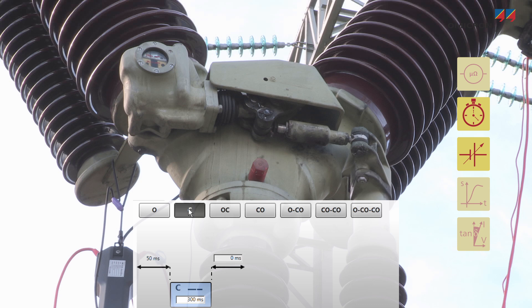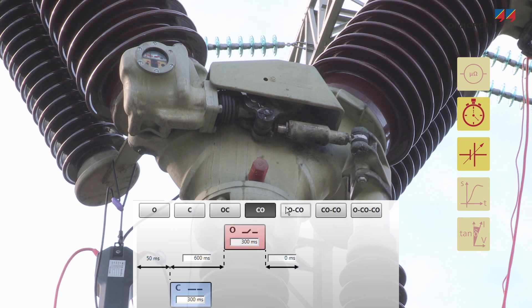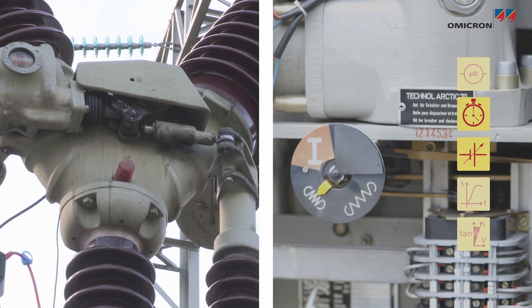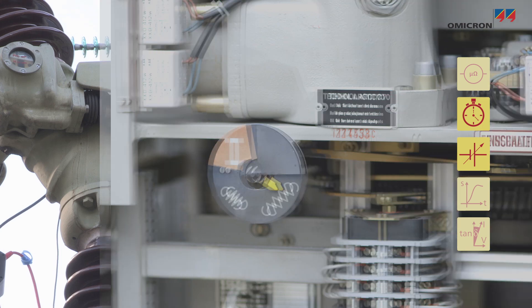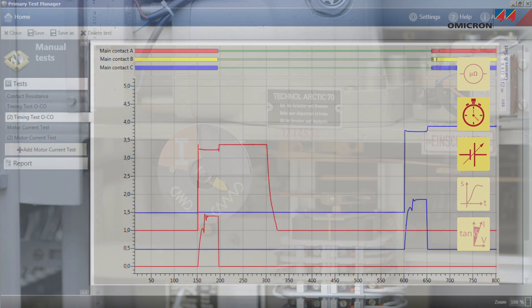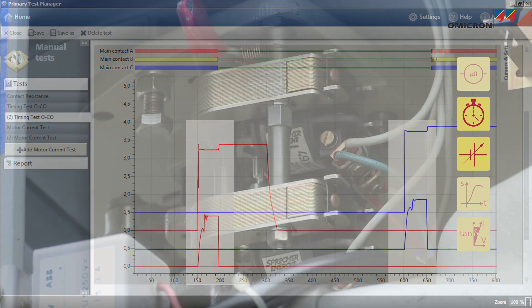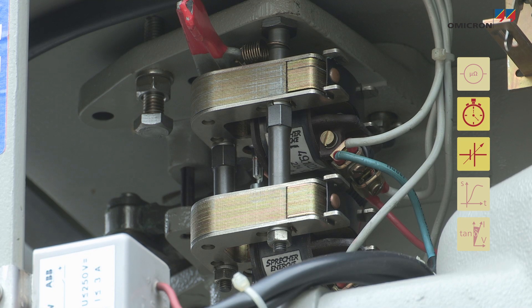An analysis of the opening and closing times of the circuit breaker contacts can validate mechanical performance. The difference between individual contacts and individual phases must fall within defined limits. Comparing these results to factory data or earlier measurements can reveal trends. Recording trip and close coil currents gives an indication of their mechanical and electrical condition as well as the condition of the latch.